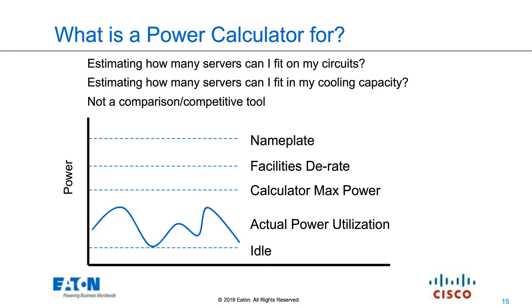And then we can give you a max power. Max power has a bit of a looser definition, because there's no single benchmark that will give you the absolute max power. It's always a trade-off. If I pick one benchmark, it will give me one power; if I pick another benchmark, it will give me a different amount of power. Your actual power utilization will have nothing to do with the calculator's max power, unless you happen to be running the exact benchmark we ran to get max power.